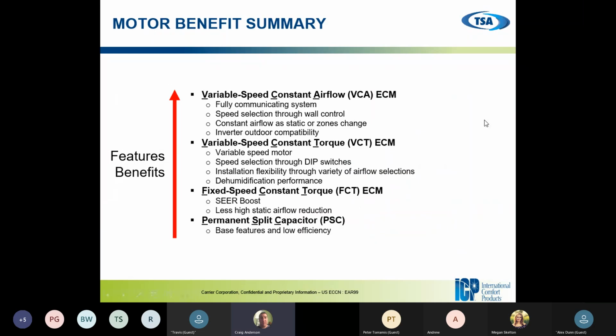So just a summary of our motors, what we have out there now. We have the fully communicating motor in our 97 and 96% communicating furnace. We have the constant torque, which is the variable speed, which is in our 96 two-stage. Our fixed speed ECM X13 motor, which is in our N95 furnace. And then our PSC motors, which is in our older furnaces, our 92s and 95% way back.